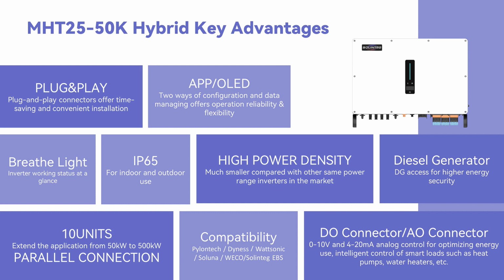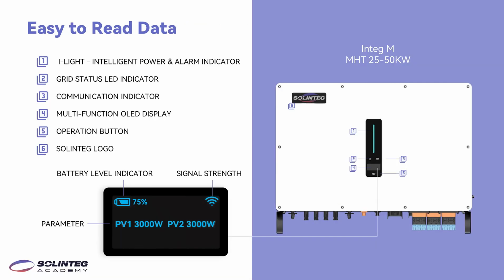And what's more, the inverter has DO and AO connectors, so it can intelligently control the smart loads such as heat pump, water heater. This page introduces the front photo of the inverter. There are three indicators. First one is the power and alarm indicator. We also call it the Breathe Light. So it shows the status of the output power and the alarm status. The second one is grid indicator to show the status with the grid. The third one is communication indicator to show the communication with the meter and with the battery.